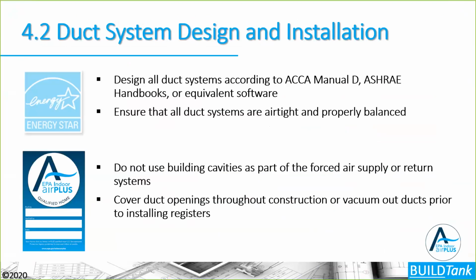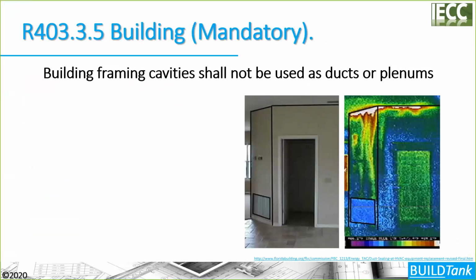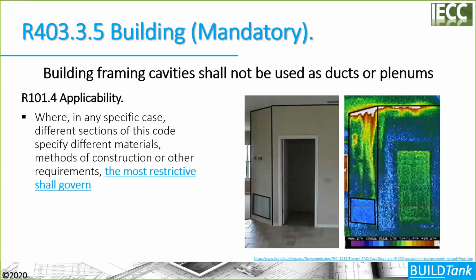So design all duct systems according to the ACCA Manual D. Again, if you're using duct systems, they have to all be inside the building envelope with some small exceptions of about 10 feet there. Ensure that all duct systems are tight and have been tested and verified to be tight and balanced so we don't get high room pressures or low room pressures, which is another requirement of the program. Don't use building cavities as part of the forced air systems. That's also an IECC mandatory requirement that says building framing cavities should not be used as duct systems. You can see the problem shown in the report here.